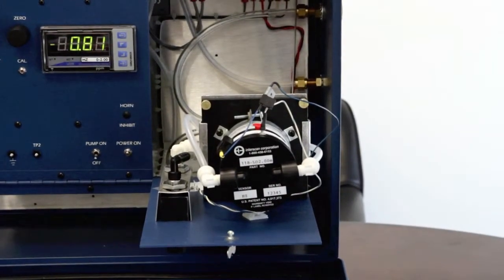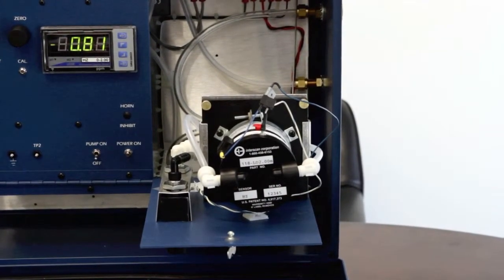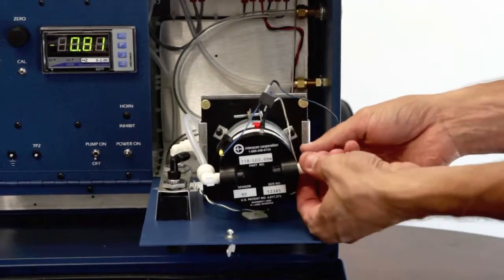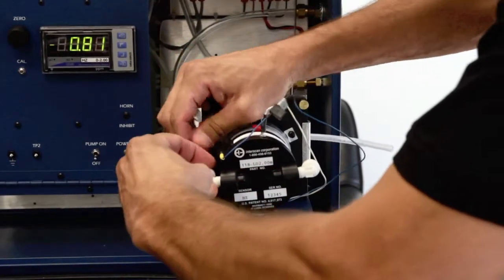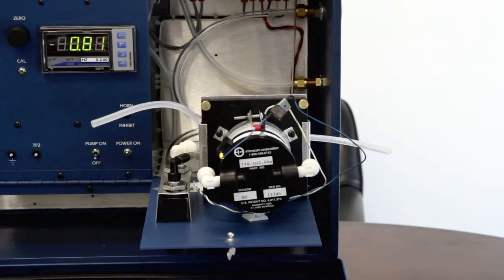Remove the existing sensor from the instrument. Start by disconnecting the tubing. Disconnect the lead wires.